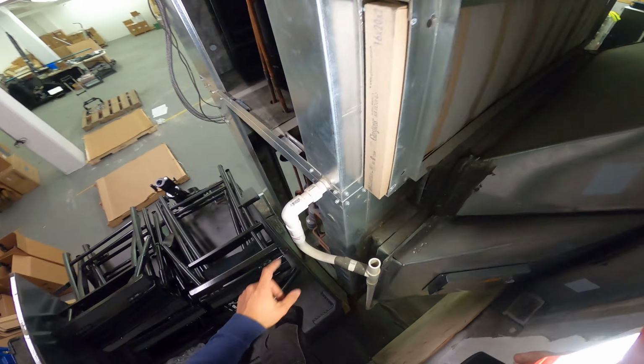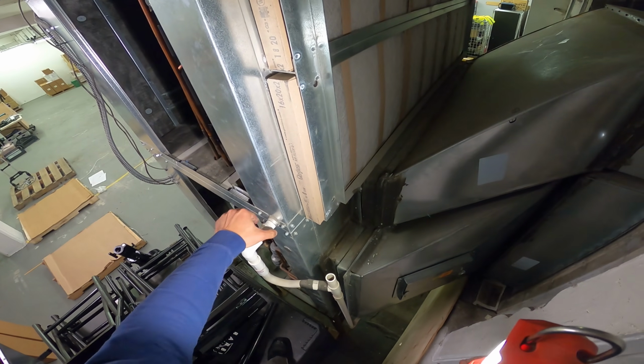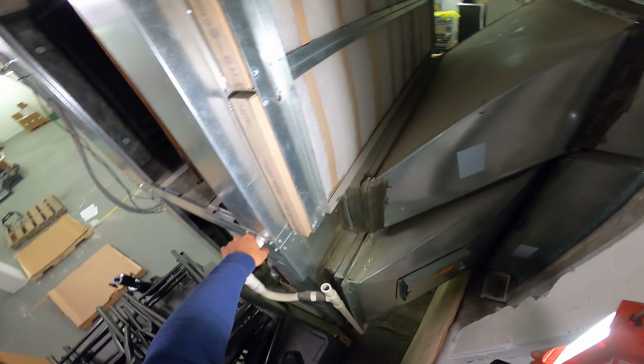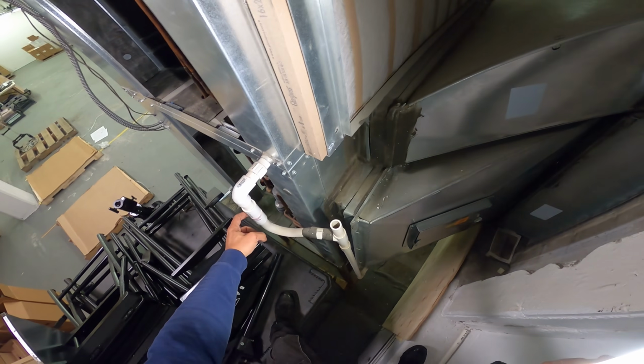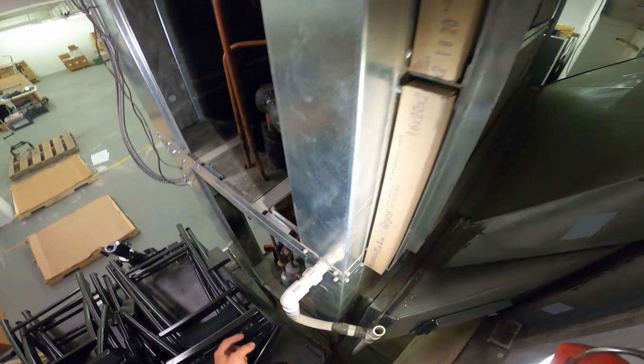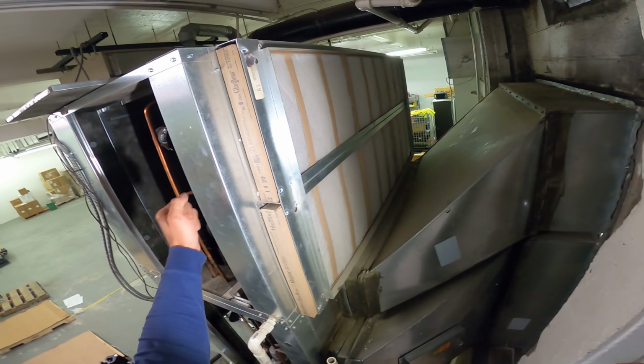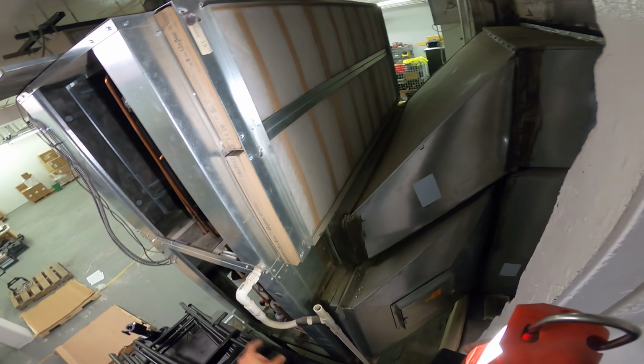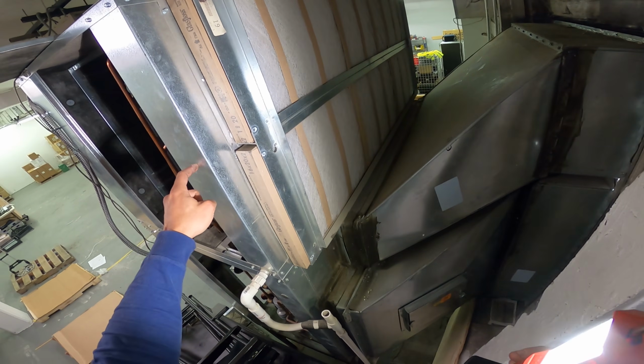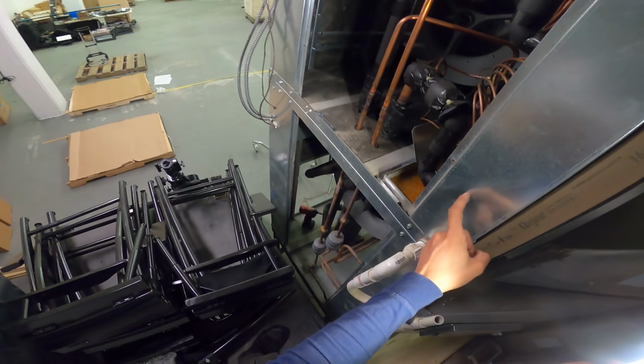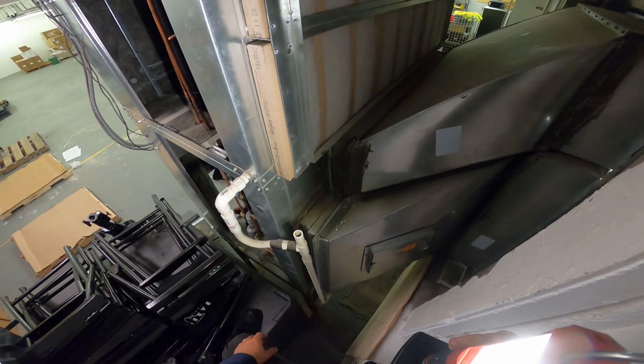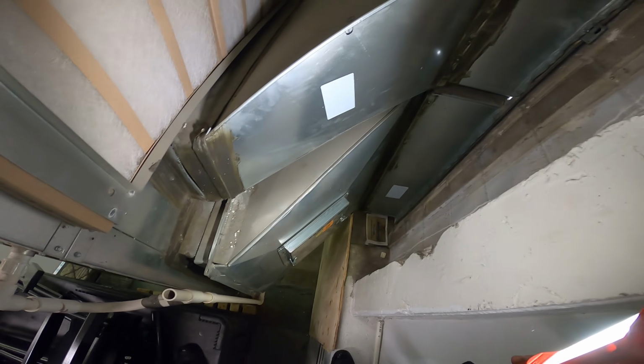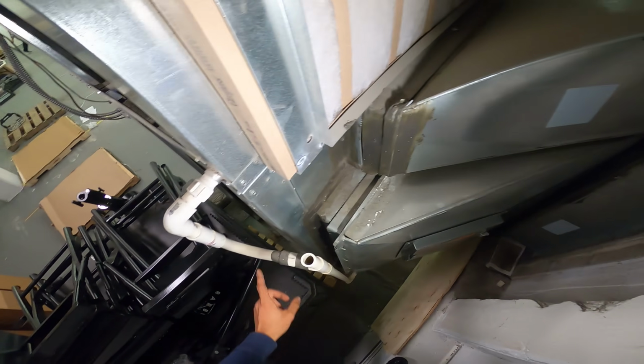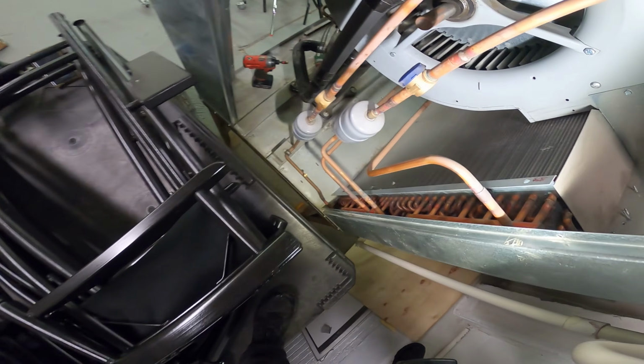Here we have a drain, so whenever you see a pipe coming out that's maybe copper or PVC like this style, you're going to know that's coming out of your evaporator. So right off the bat, without even opening this unit, I know that this is the evaporator section. Also, I can see this duct is leading outside, and that's how I know that is my condensing unit.